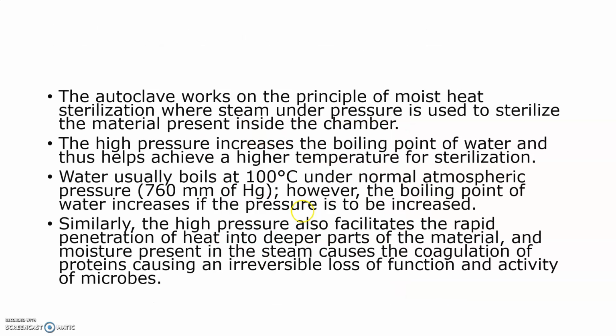An autoclave works on the principle of moist heat sterilization, where steam under pressure is used to sterilize the material present inside the chamber. So what happens inside? When the pressure starts increasing, the boiling point of the water also increases, and this helps to achieve a higher temperature for sterilization. The water usually boils at 100 degrees Celsius under normal atmospheric pressure. When the pressure increases, the boiling point of the water also increases.